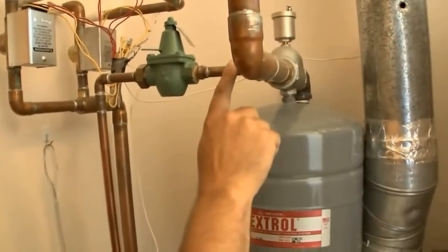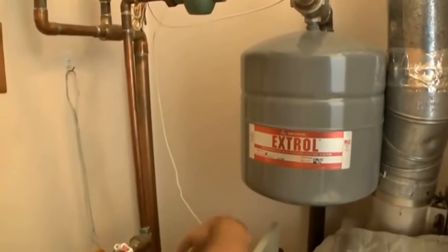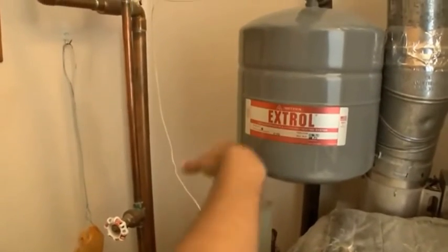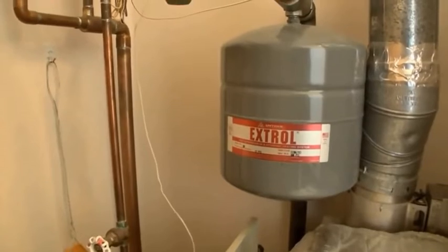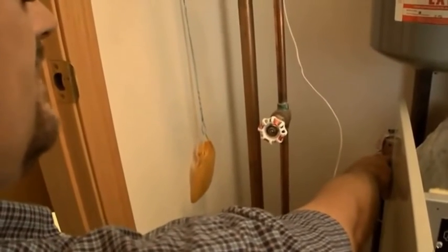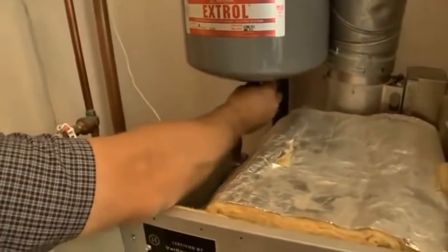And it's a chain reaction. Then we add more water. And when it shuts down and cools off, it heats up, it gets to a high pressure, and we just keep running new raw water through this over and over. And in this case, the drain for the relief valve is down in the crawl space. So you really wouldn't know if it was occurring. It would be nice if the drain for the relief valve went into a pan, and then you could see when that happens. That would be a better way of having it than the way it is.